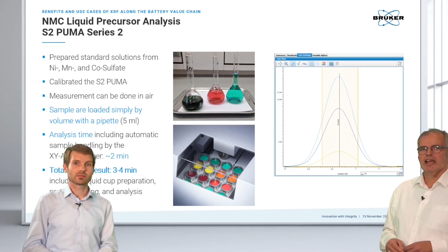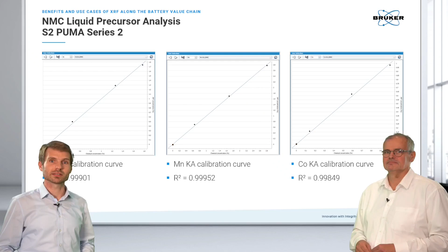Actually, when we see here the calibration curve, it means they are straight, so it shows it's a straightforward process, and we see the correlation coefficient is close to 1. I guess it's a no-brainer. XRF can be calibrated and can be very accurate. These are the calibration curves here for the 3 elements. In this case, we just focus on the majors. Of course, we can also calibrate the traces and contaminants in the system and achieve a very good calibration curve and precision. And one brief look into our software here.